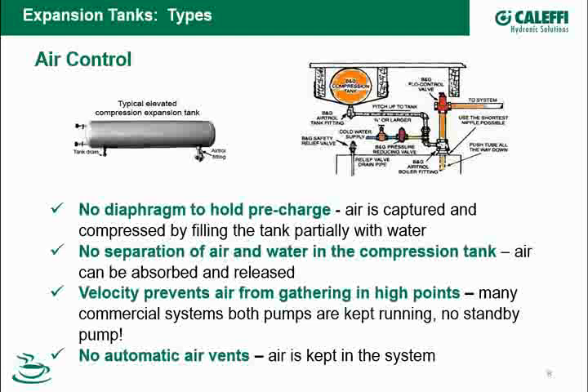For instance, if I'm running at 12 psi of pressure, I have to fill that tank up and compress the air by filling the tank up 45%. The other 55% that's left over now becomes my expansion volume. The other big thing about the compression tank, and why it's referred to as air control, is that in that tank there's no separation between the air and the water. So air can be absorbed into the water and it can also be released in the water. So what happens is the air in that tank is constantly migrating into the water and back out of the water. Now, because of that, we cannot design around eliminating the air. It's about controlling the air.